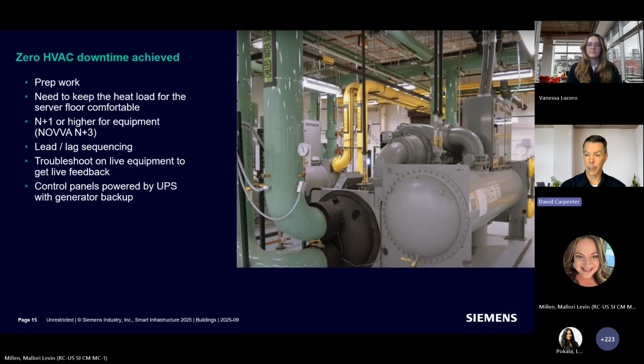changeover. As soon as there was actual equipment hooked to it, we wanted to sequence that lead lag. And that's important because the pieces of equipment as pictured here, this particular site was Carrier centrifugals, 750 tons, 4 of them. And every piece of equipment is going to have its own startup minimum times, times that we want to see it operate, etc. And make sure that those are all in line with the operating plan for the customer. And then we can troubleshoot that.